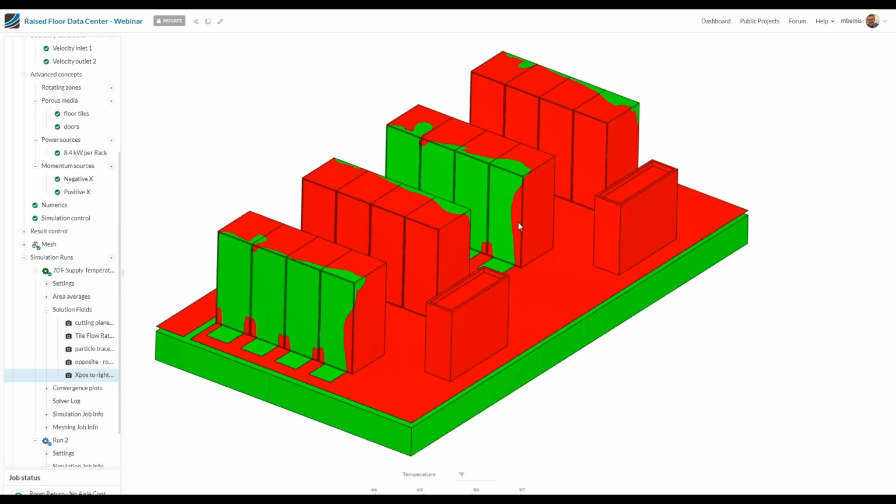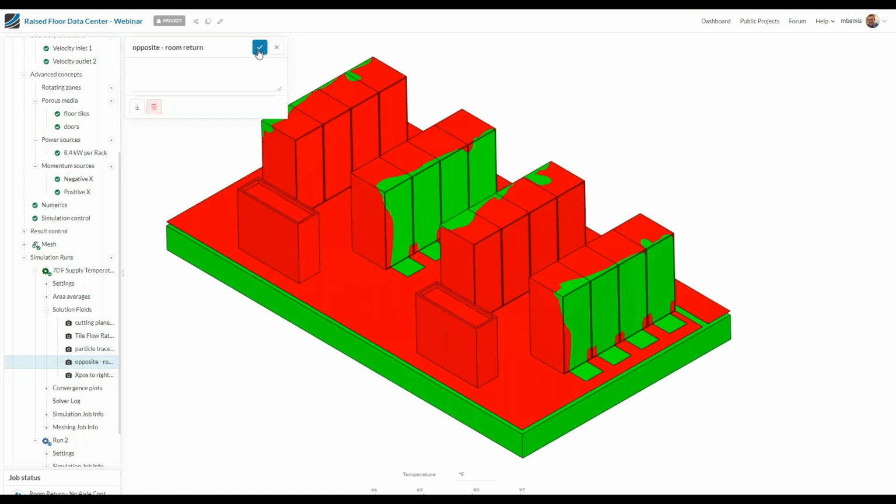Essentially, one of the challenging things as a data center operator is that you may have DCIM infrastructure in there, you may have sensors in there, but it's not one value. It changes based on the position. And that's where CFD and SimScale can really give you insight. So again, we've got problems on the rack which is closest to the CRAC units. Just check it out the opposite direction. Tells the same story. These are the problematic racks here.